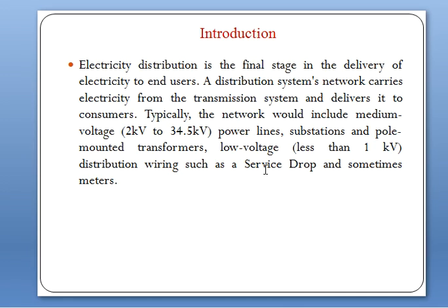Within these networks, there may be a mix of overhead line construction utilizing traditional utility poles and wires and increasingly underground constructions with cables and indoor or cabinet substations. However, underground distribution is significantly more expensive than overhead construction. In part to reduce this cost, underground power lines are sometimes co-located with other utility lines in what are called common utility ducts.